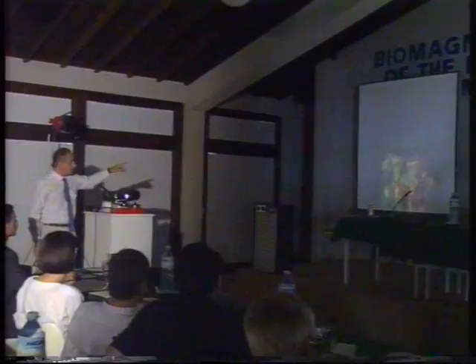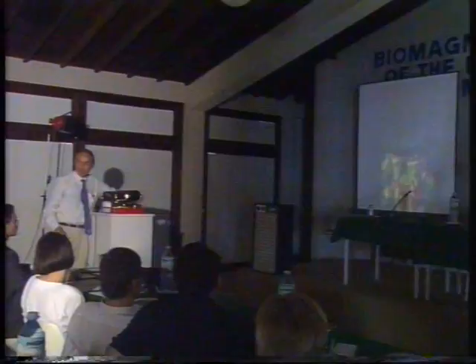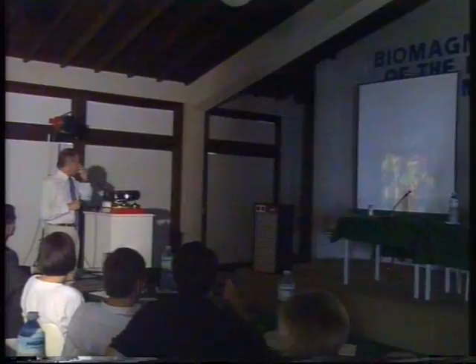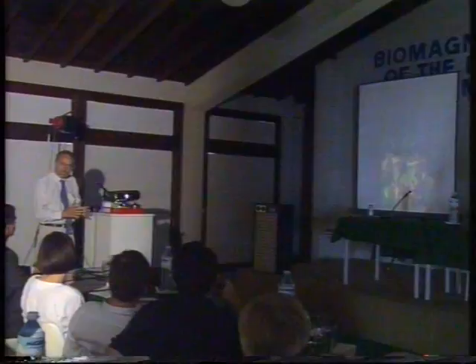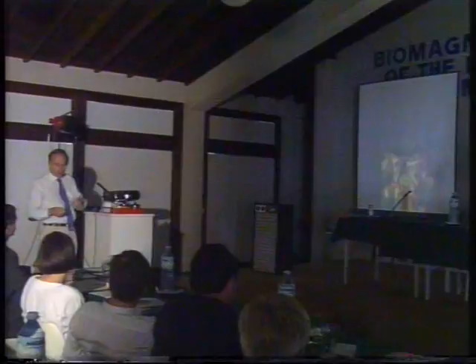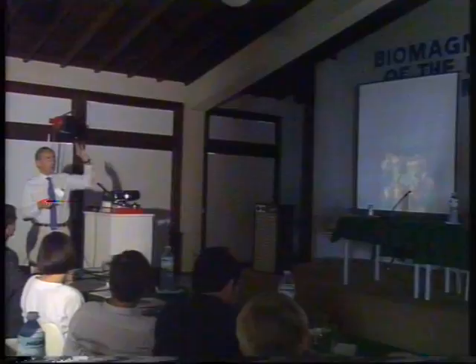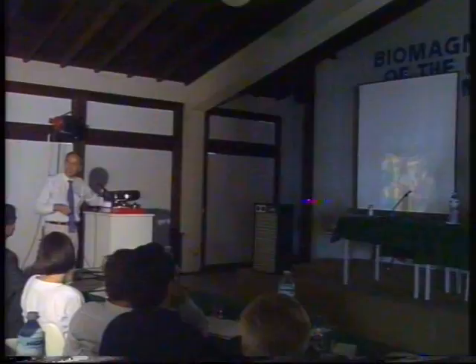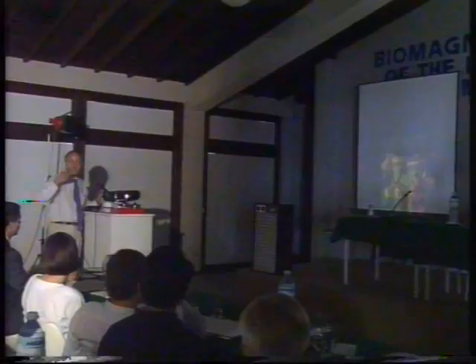We have a least-squares criterion calculated and visible on the monitor. When the fit is perfect, we can display on the monitor the real 3D and follow the trajectory of the tool in order to place the screw in the vertebra. The trajectory extensions are shown on the monitor, and we can interactively adapt the tool and define the most precise strategy.